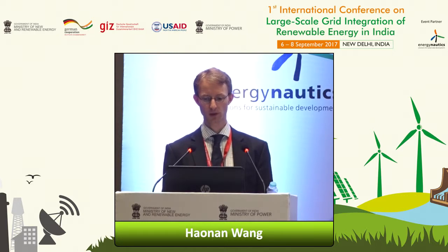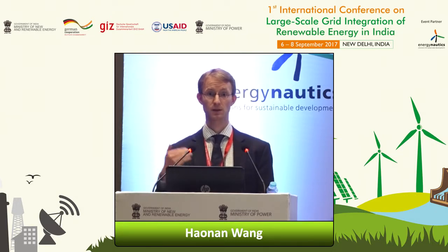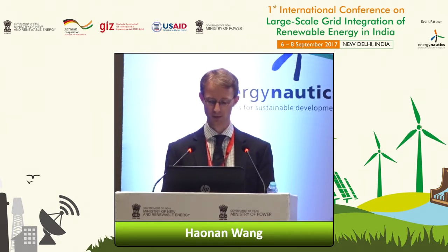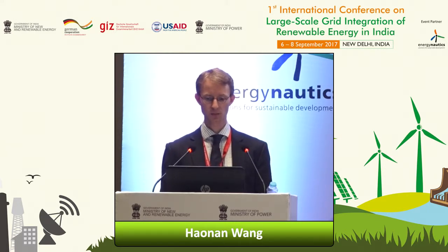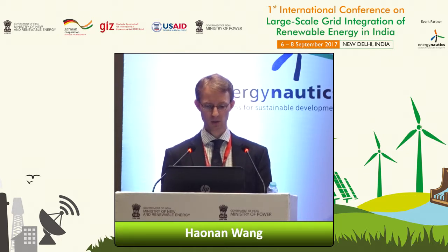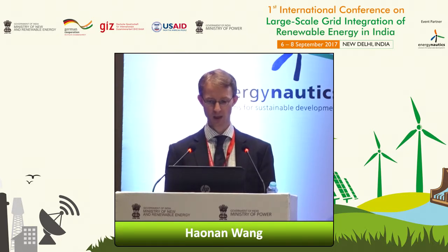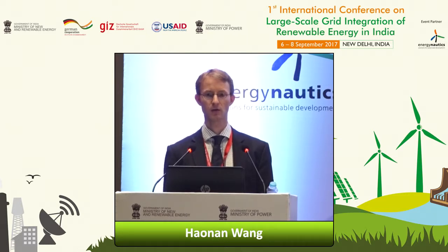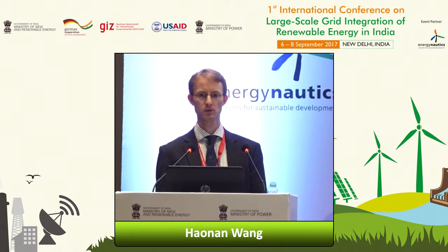We are looking then at the reactive power flexibility that is available at the grid supply point towards transmission, distributed across different voltage levels. This is a kind of reliability and flexibility checkup. What we can see is that we have a very high flexibility here in the blue area, and then we have a lower reliability. This now depends on the availability of photovoltaic or wind turbines.